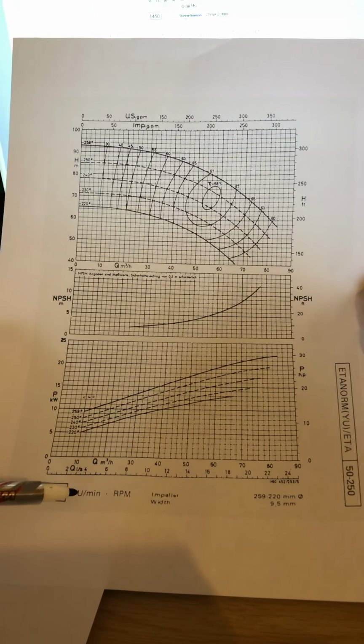And so if you look at these values, you'll get a bar here on the right hand side. This one says Etanorm, so that is the make. The pump series is that ETA. The nominal diameter of the outlet is 50, and the nominal diameter of the impeller is 250. So that's the make, that ETA is the pump series, the diameter of the outlet is 50, and the nominal diameter of the impeller is 250.